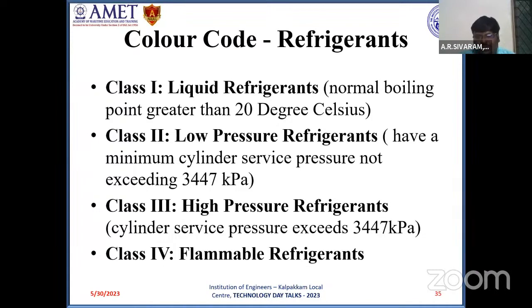And coming to color code. For the identification of refrigerants, in order to differentiate one refrigerant from another, a color code has been introduced. For the purpose of color code, AHRI, the Air-Conditioning, Heating, and Refrigeration Institute, classifies refrigerants into 4 classes: class 1, class 2, class 3, and class 4, which are liquid refrigerants, low pressure refrigerants, high pressure refrigerants, and flammable refrigerants. Normally for liquid refrigerants, the boiling point is greater than 20. For low pressure refrigerants, the cylinder pressure does not exceed 3447 kilopascal, and for high pressure the cylinder pressure exceeds 3447 kilopascal, and the last one is flammable.